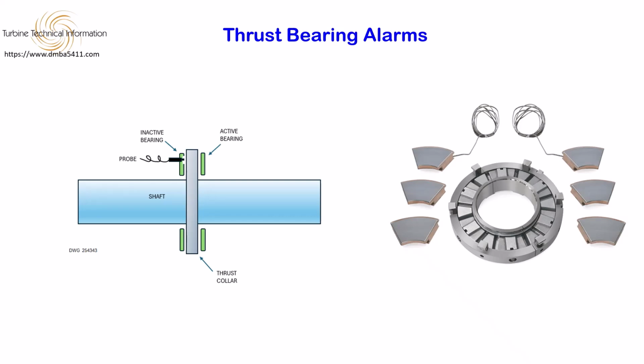Thrust bearing temperatures. Thrust bearing temperatures are often monitored using resistance temperature detectors. When the temperature increases, it is an indication that the thrust bearing is worn. In many cases, bearing temperature data is considered a better indication of the actual condition of the thrust bearing than axial positional measurements.